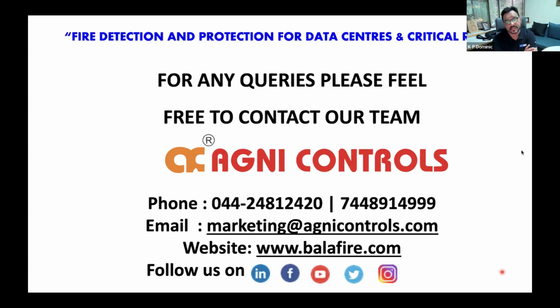It can be tested, but whereas a clean agent, whatever the supplier gives in writing, we don't really know whether there is a clean agent inside, whether it is only nitrogen. So that's the game changer. As Arun said, you can always test the high pressure water mist, but not the clean agent. If you test it, you have all the gas out, and again, same cost as in new installations. So that's the tricky part of this clean agent system.